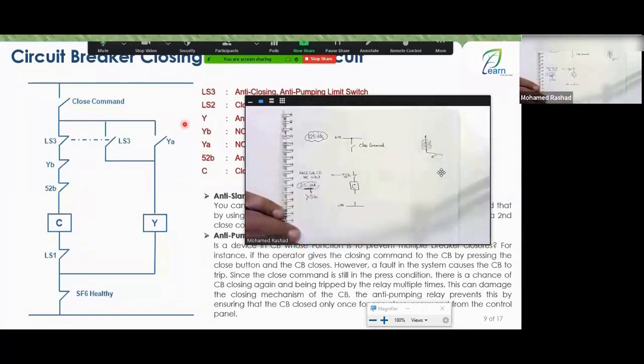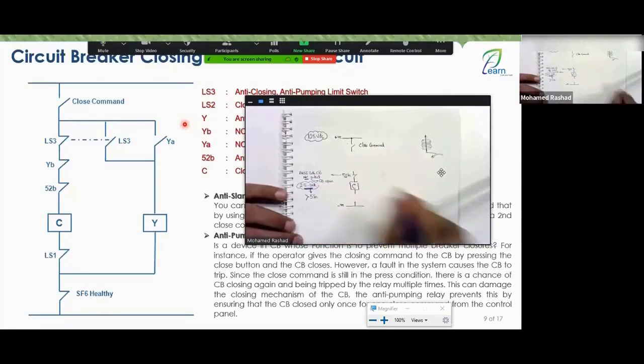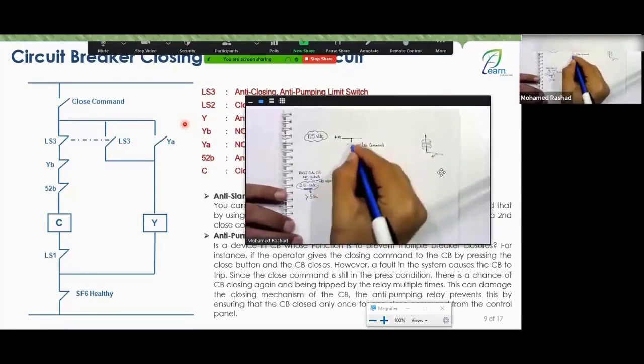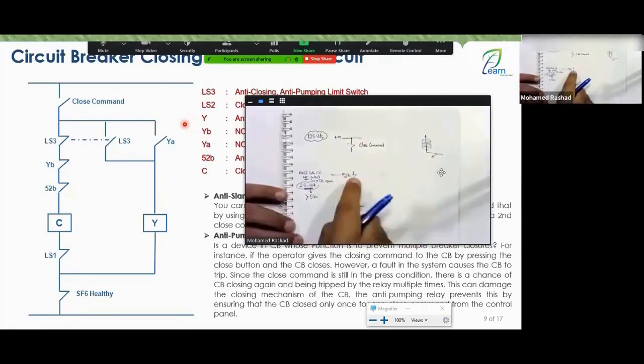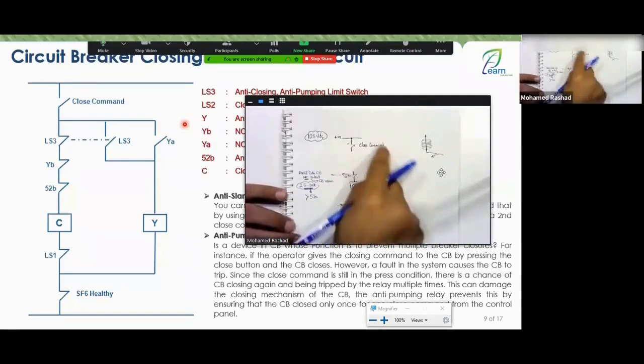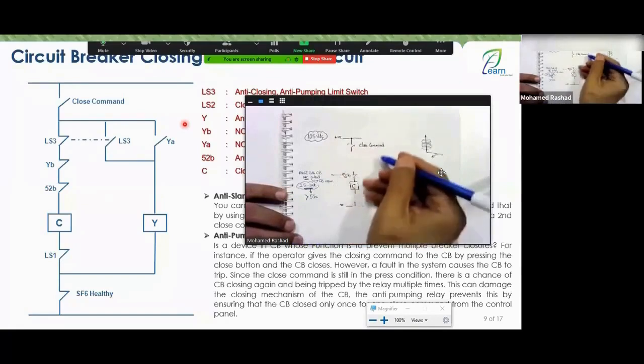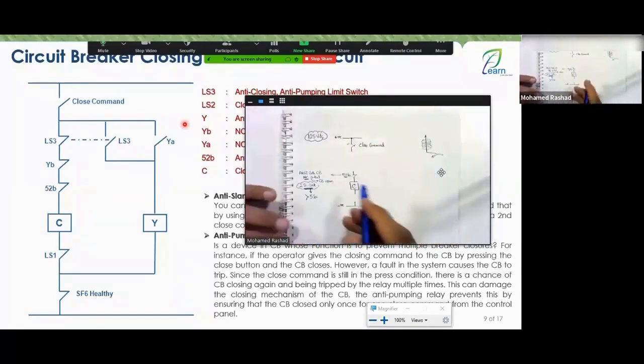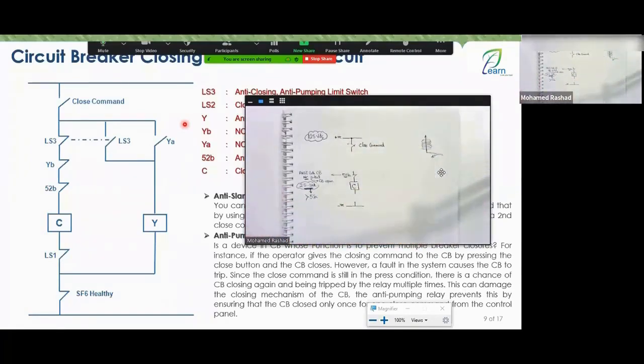Okay, so when is this contact normally closed? The term normally closed must be related to something. As long as the circuit breaker is open, this contact is closed. So if you give me a close command and the breaker closes, what happens to this contact? It opens. So if you give me a close command again, the DC won't reach the closing coil, which means I protected the circuit breaker from burning out.